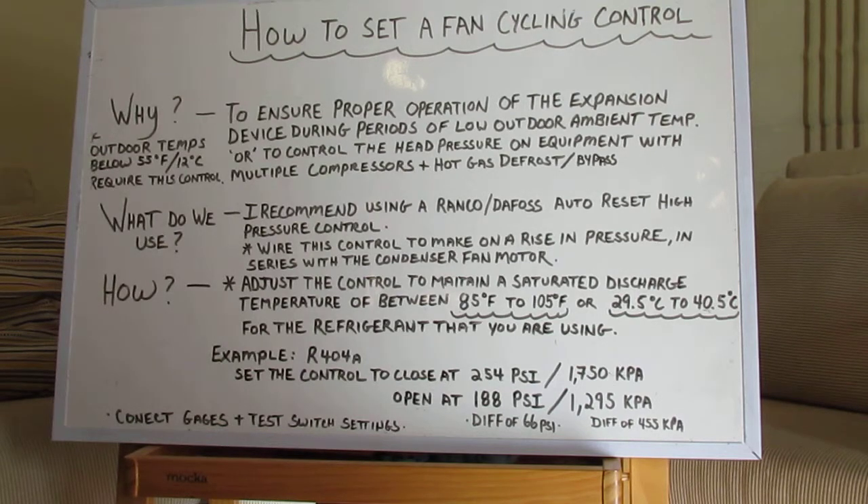So when do we have to put this control on? Any time you get an outdoor temperature that drops below 53 Fahrenheit or 12 degrees Celsius, typically you may require this control. At 12 degrees Celsius, it's sort of on the line whether or not you're going to use this control, but it all depends on what system you're trying to control refrigeration wise.